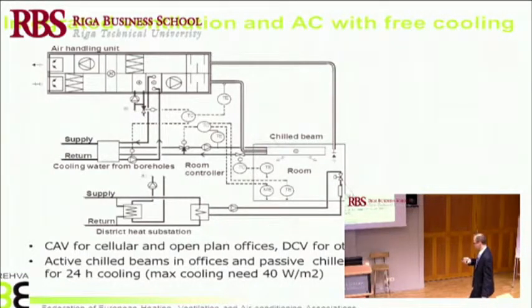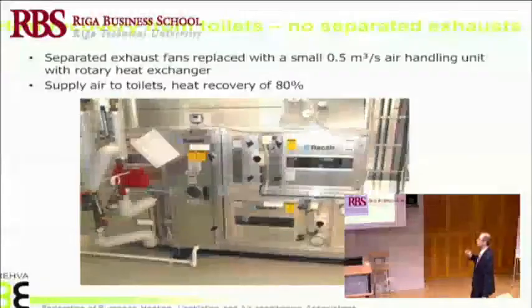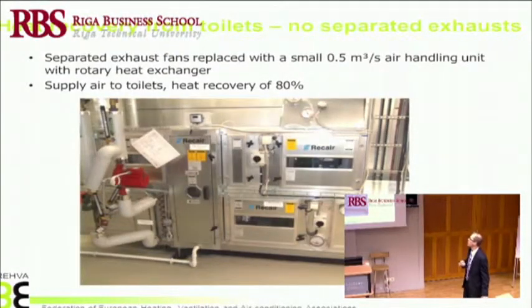And when you have a large air handling unit, you can use high efficiency components and achieve very low energy use. Actually, it was a constant volume system for office rooms and demand controlled ventilation. So there were about 5 air handling units and separate air handling units for the demand controlled ventilation system for other rooms which are not constantly occupied, as for example open plan office or office rooms. So this was also used. What's very specific, it should be a world record heat recovery from the toilet air with 80% heat recovery efficiency. And it was done with a rotary heat exchanger.